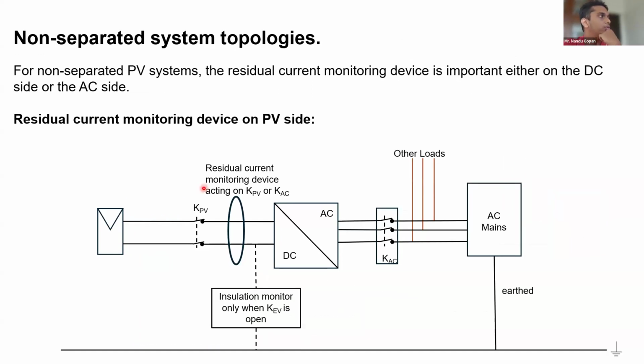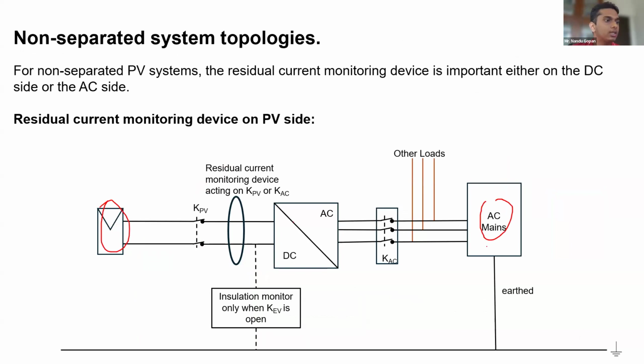Now, if you are going to a non-separated earth system, there is a solar PV, there is an inverter, and this will be the discom's system referencing conductor. So the system referencing conductor will be earth. In this case, from the inverter till the point of commencement of supply, till KAC, there won't be any system referencing done. Equipotential bonding and other protective measures will be done, but system referencing won't be done. Only in the AC mains will the system referencing be connected.